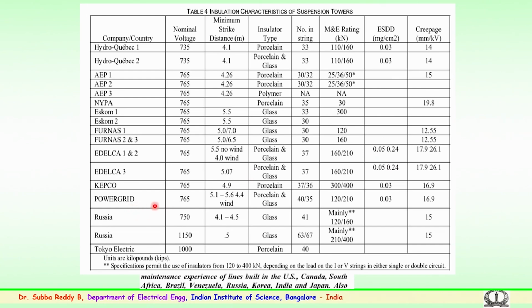This particular information, adopted in this country by the Power Grid Corporation of India, shows a 765 kV insulator string where we have a minimum strike distance of 5.1 to 5.6 meters because of the wind prevailing in that particular belt, and we use porcelain or glass insulators, with 35 to 40 insulator discs connected in series, as I mentioned earlier. The mechanical ratings of 120 kilonewtons and 210 kilonewtons are presently employed, and 0.03 is the equivalent salt deposit density, that is, the pollution zone we are employing, and 16.9 is the mm per kV. You can compare this with others. We have higher pollution areas, which is one of the reasons we go in for higher creepage per kV levels.